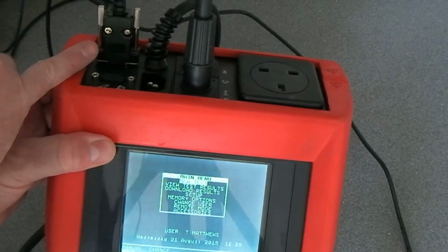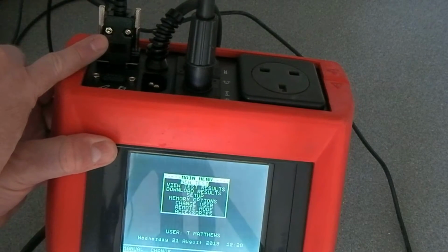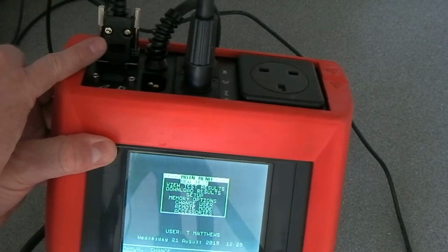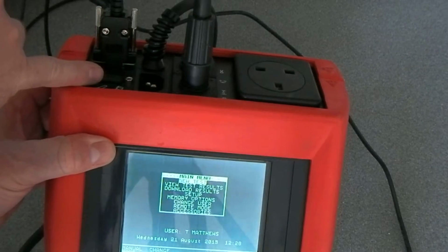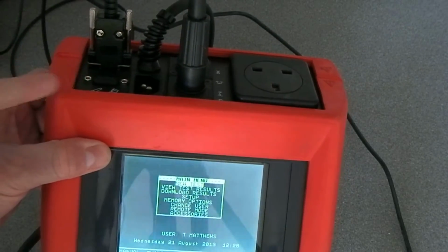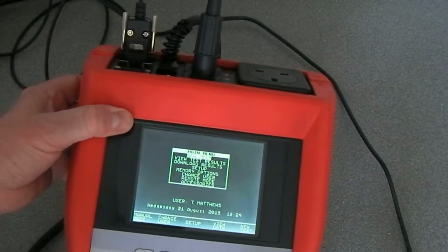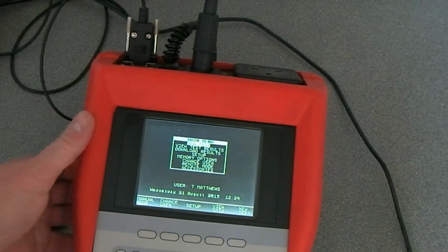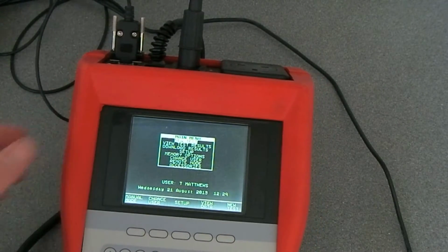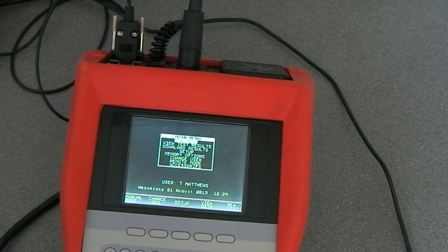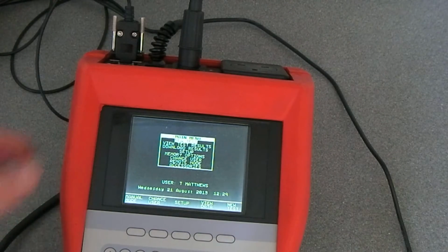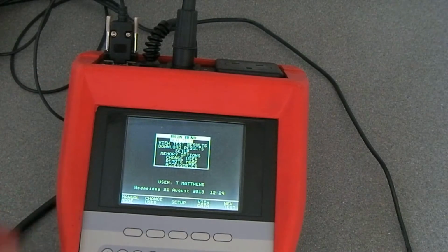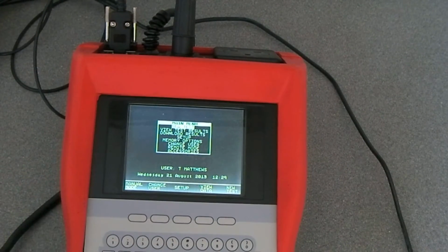You then have a communication port to the laptop. That's just a standard serial connection, and just above it you have a connection for a printer or barcode reader. I haven't got the barcode reader. In my case I'm not going to be retesting the equipment because it's just being returned by post to customers, and there is no retest requirement, so it's purely being done to assure everybody that the repair is safe, and that's that.